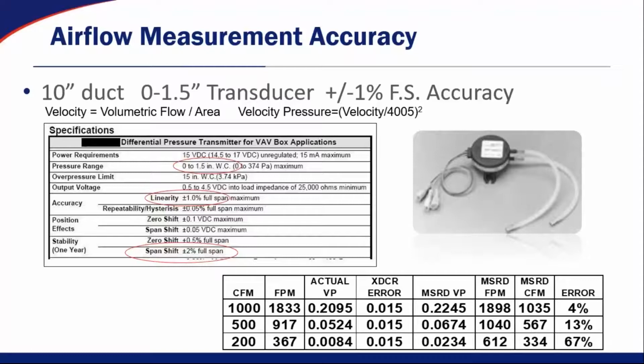If I add my transducer error onto that, my measured velocity pressure is now 0.2245. My measured velocity is 1898. My measured CFM is 1,035. And that's a 4% error at 1,000 CFM, which doesn't look too bad.